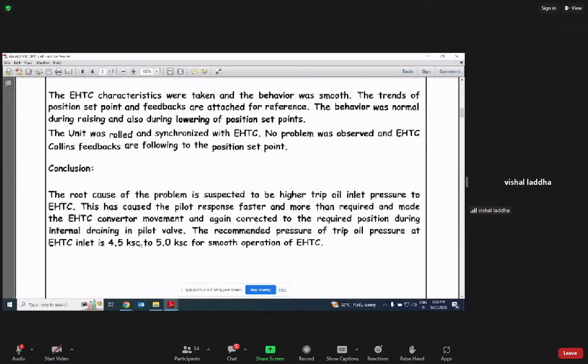So what was the conclusion? The conclusion is very simple. The root cause of the problem is suspected to be higher trip oil inlet pressure to EHTC. This caused the pilot response to be faster and more than required, and made the EHTC converter movement correct the position again to the required position during internal draining in the pilot valve.